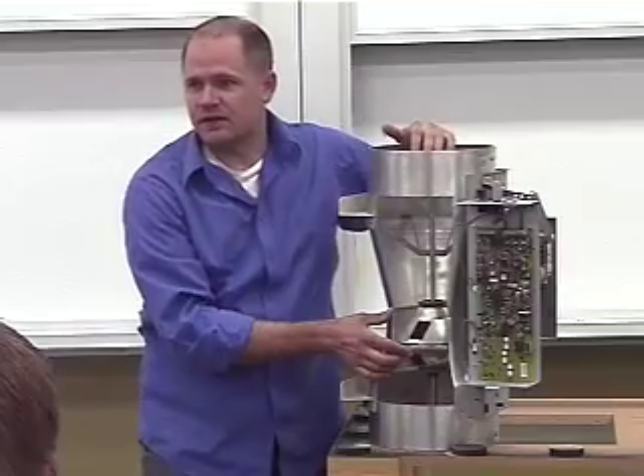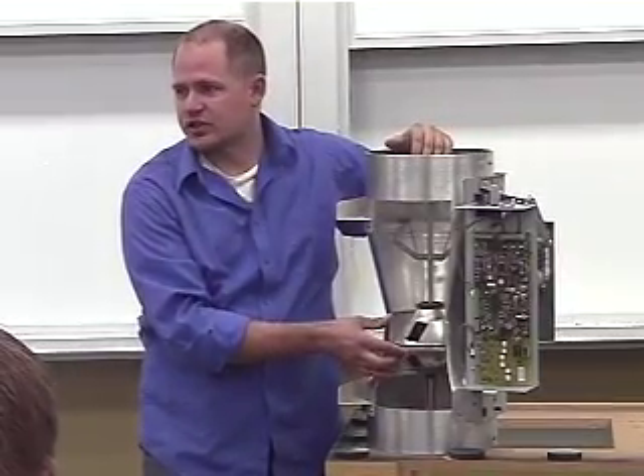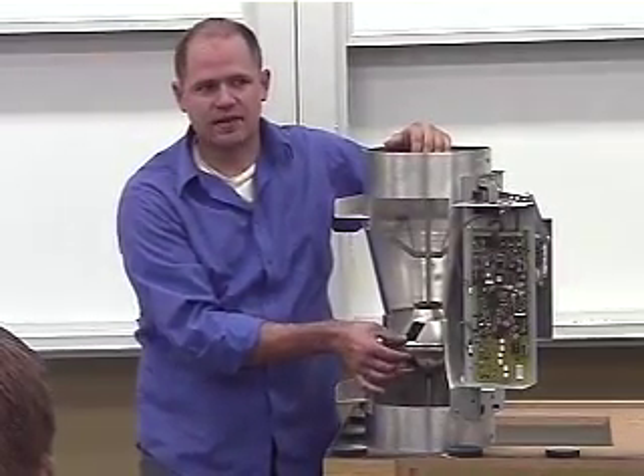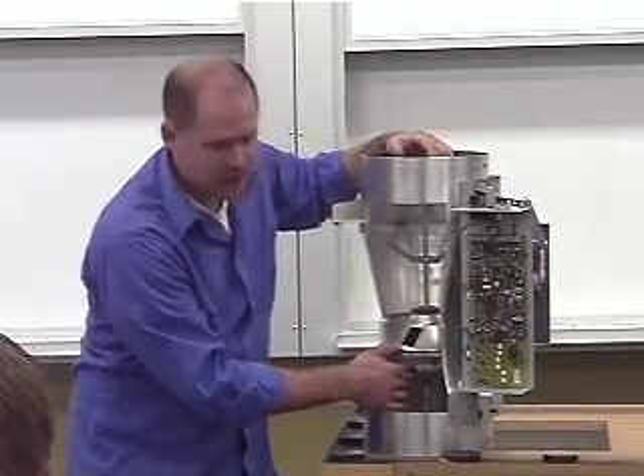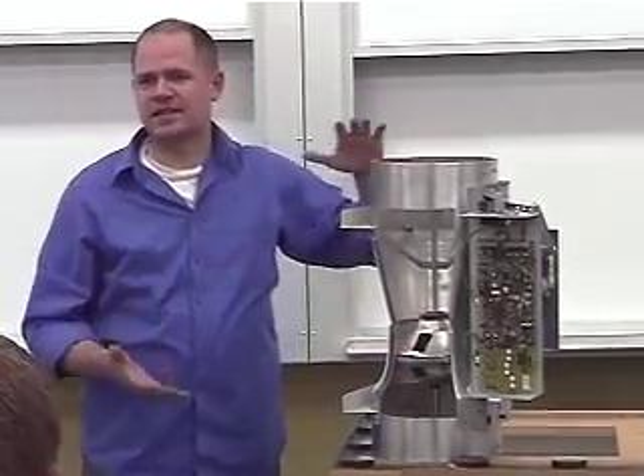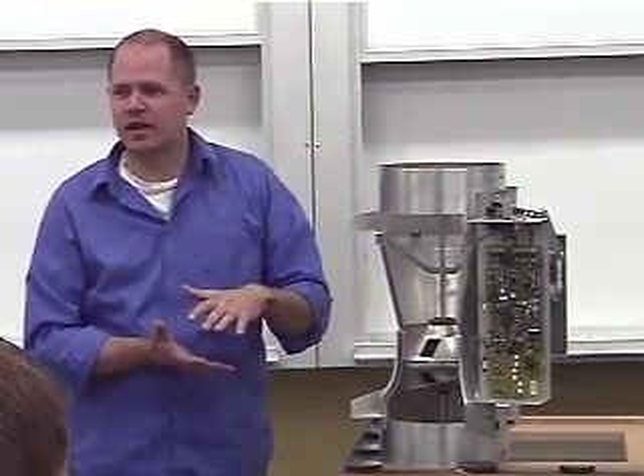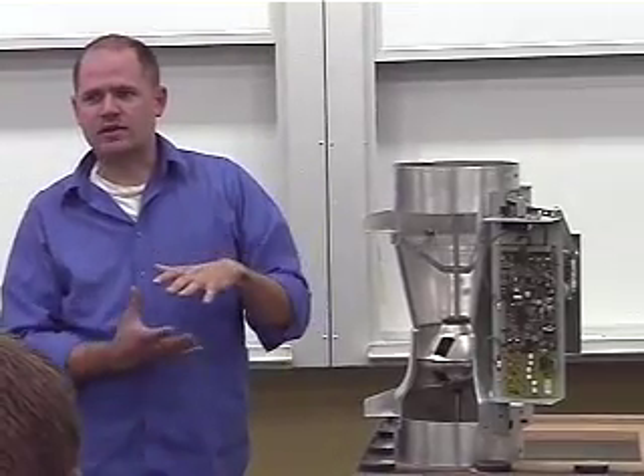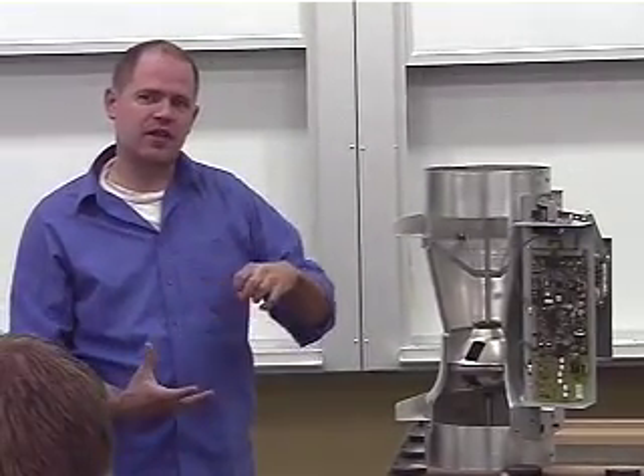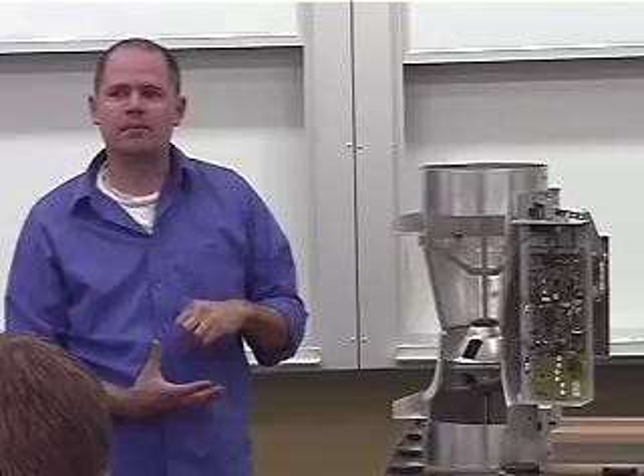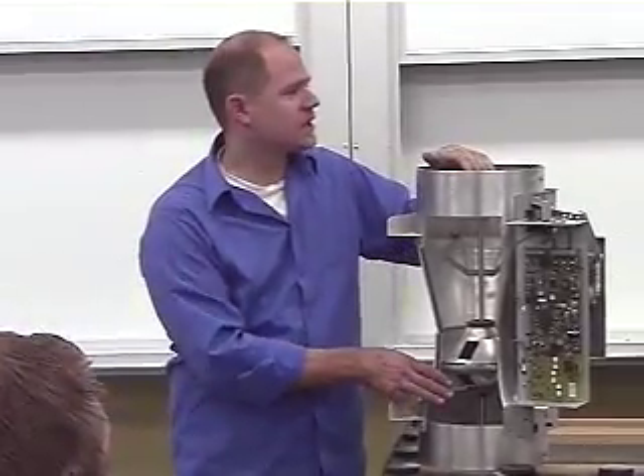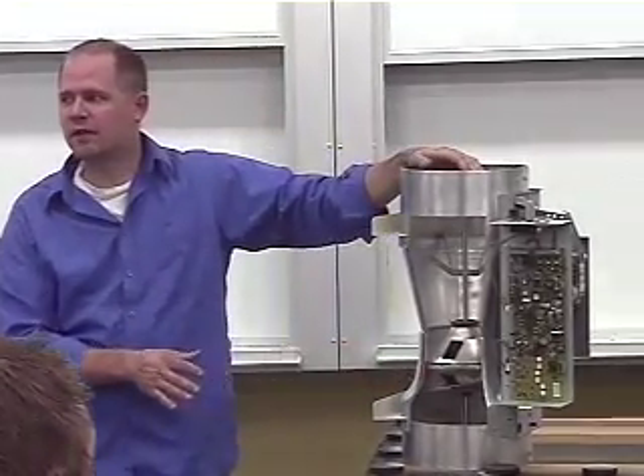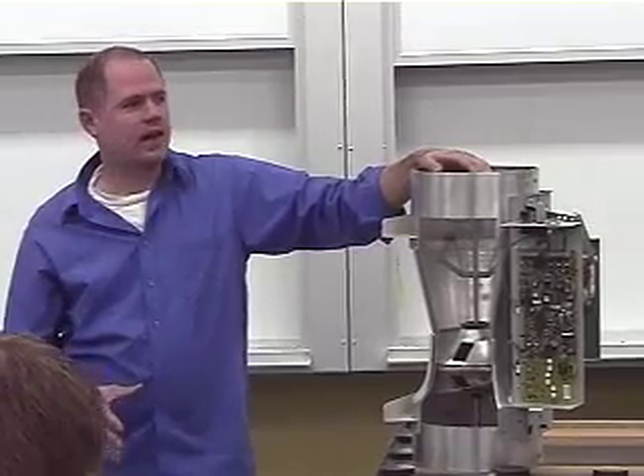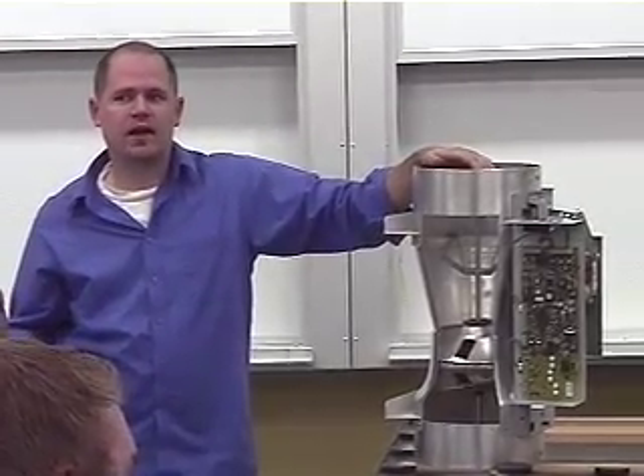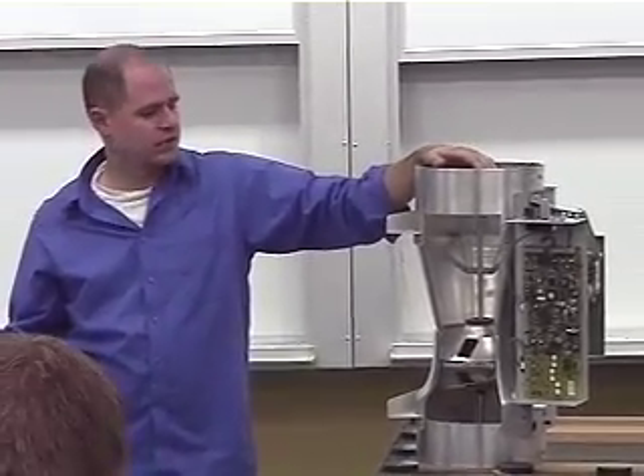I don't know if you can see it from there, but you're welcome to come up right after. I can show you the inside of this and how that works. But this spring is not just a linear spring that has the same resistance across the whole path. It varies based on how hard it's being pushed down. So the harder it gets pushed down, the more resistance it supplies. That means this can maintain its airflow for a larger range of supply pressures.